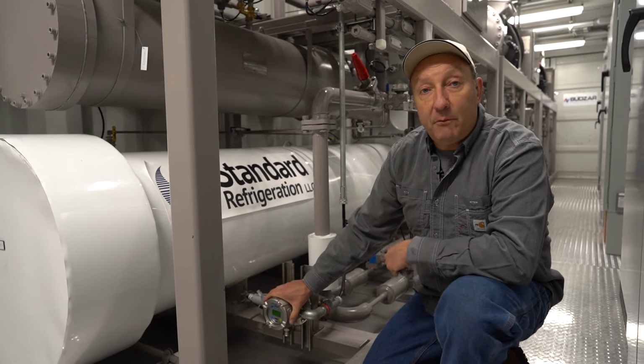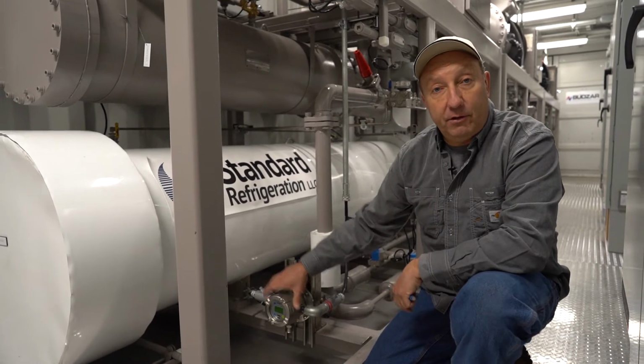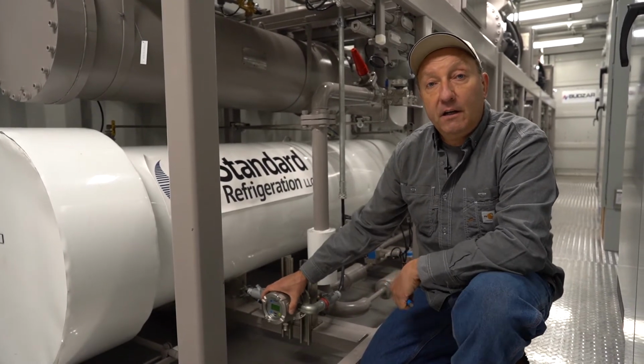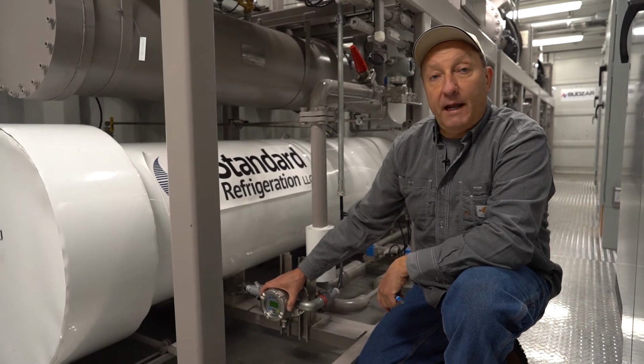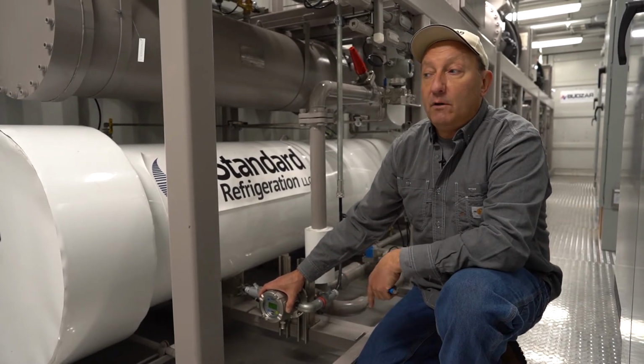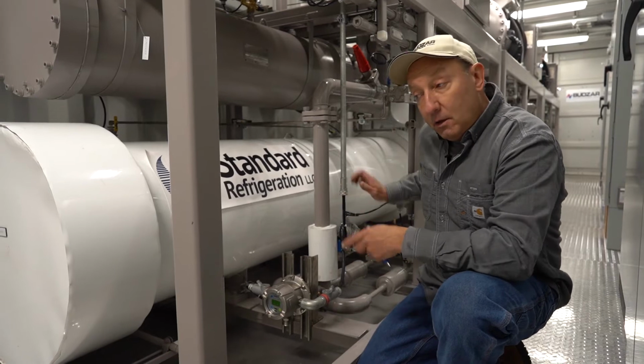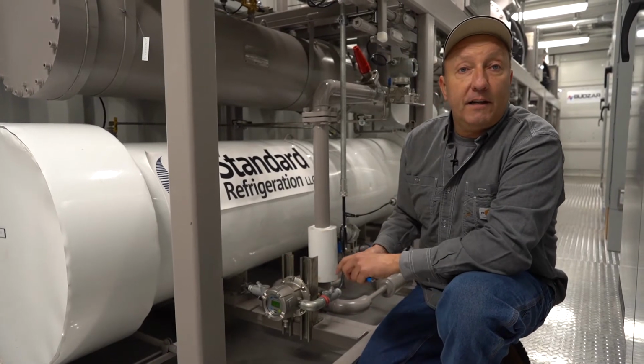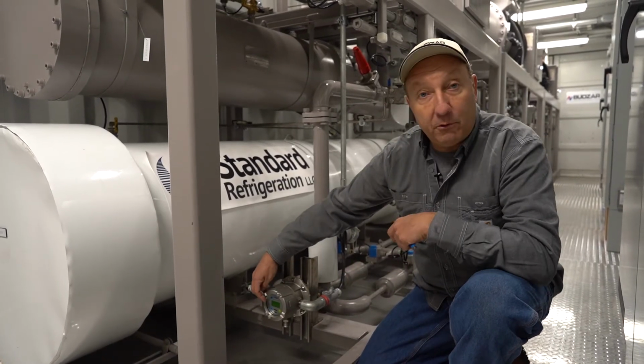In the event that we do have a propane leak and trips the LEL propane sensor, it will trigger all the alarms, but as the ventilation system triggers and we move the refrigerant out of the container, the LEL display will reduce.